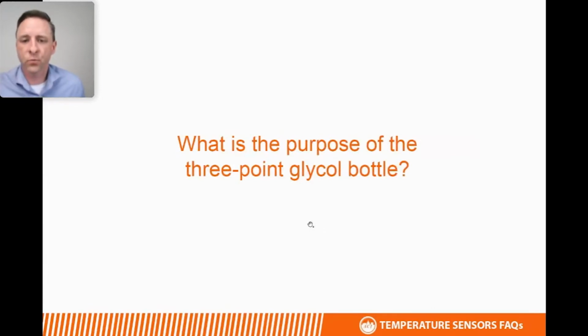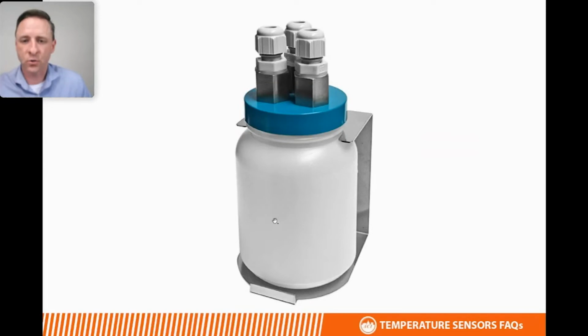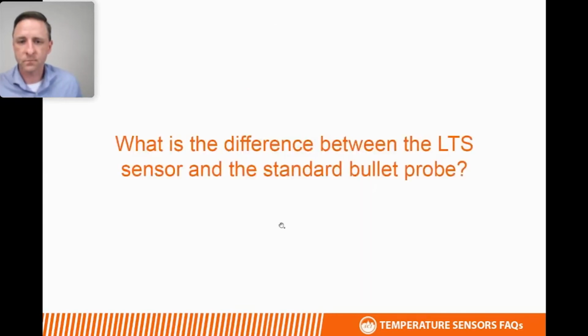What's the purpose of the 3-point glycol bottle that you see on your screen? We see a number of applications, specifically pharmaceutical storage, where redundancies are required. And so this allows for multiple sensors to be installed in the same cooler, same freezer, and allow for multiple redundancies in one area. What's the difference between the low temp sensor or LTS probes and the standard bullet probes? The LTS probes are built out of some different materials. The sensing element is built a little differently to withstand the lower temperatures. And there's also some physical size differences.